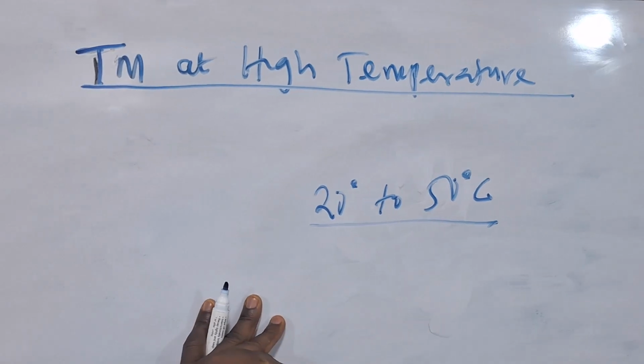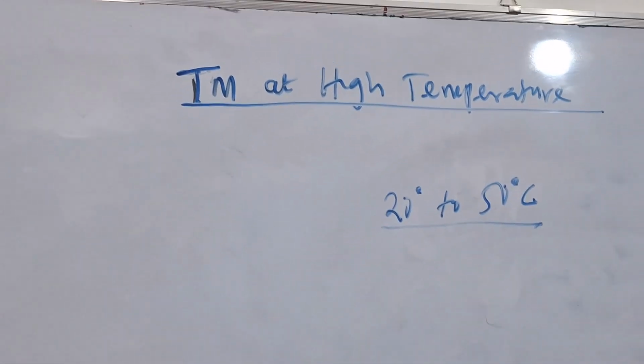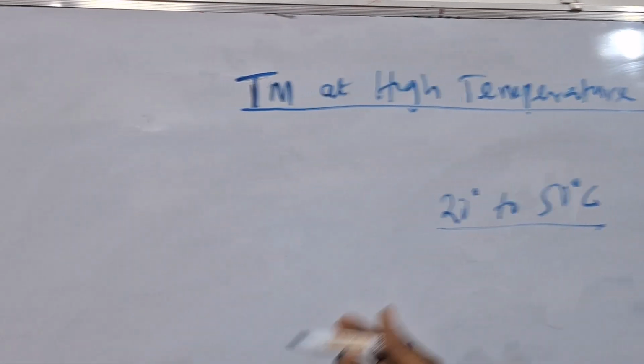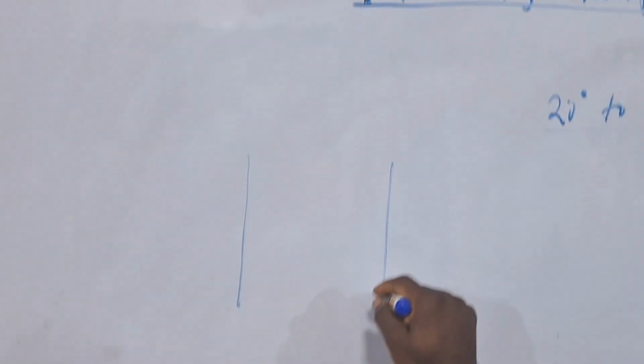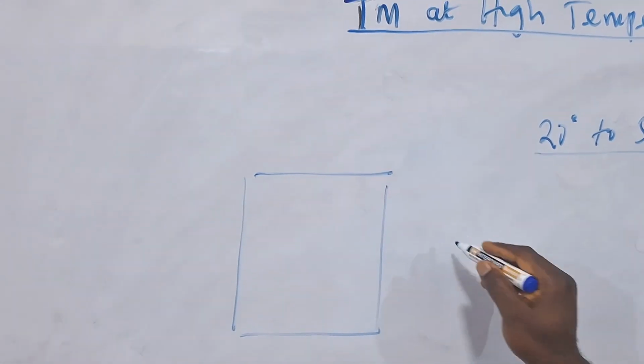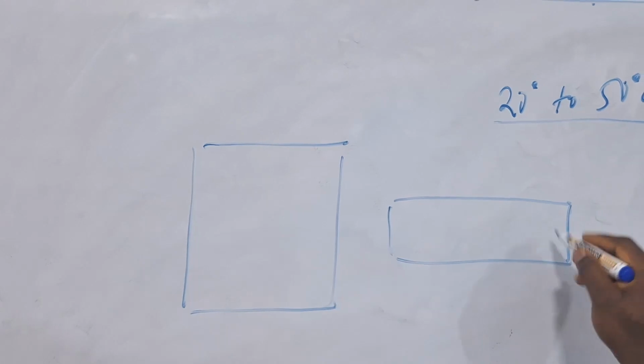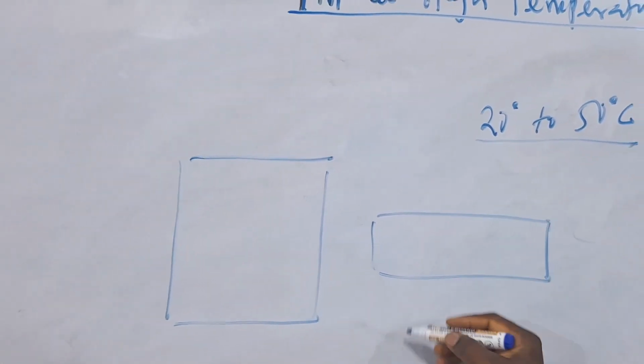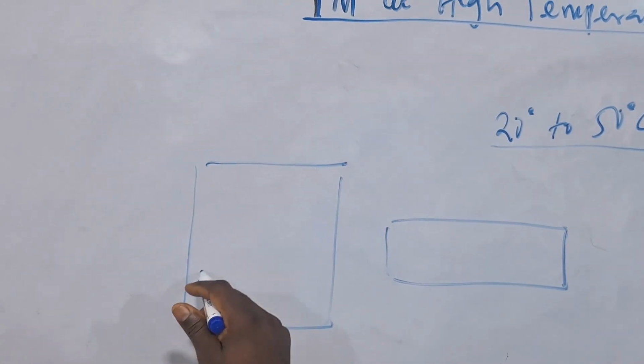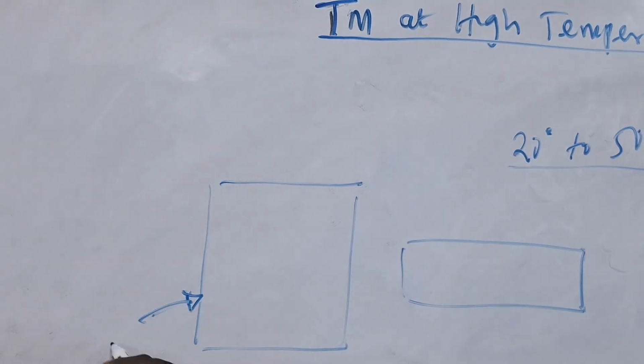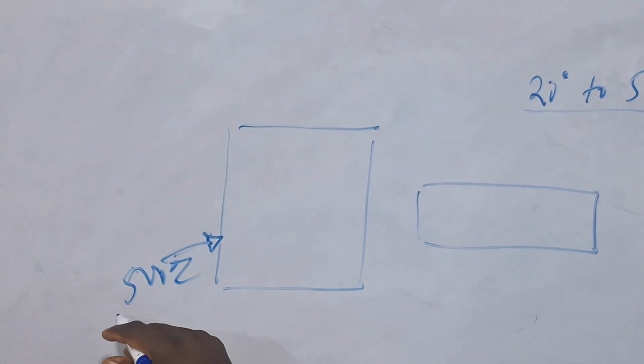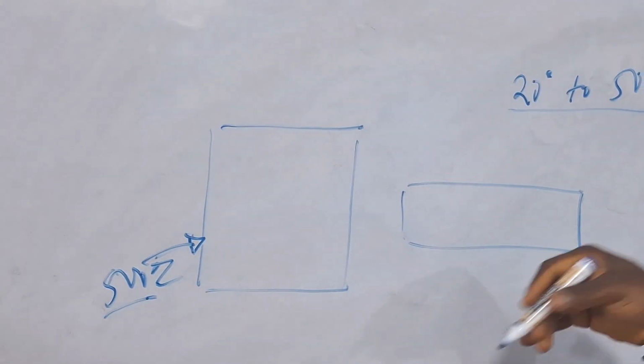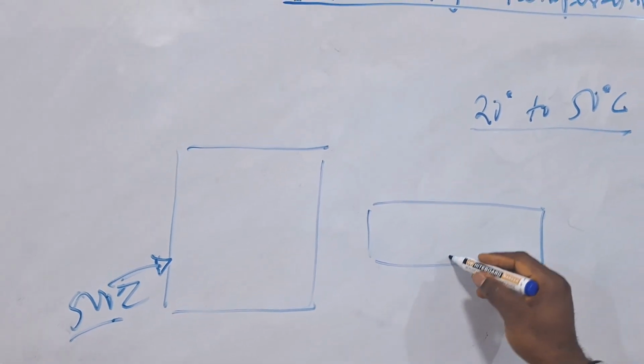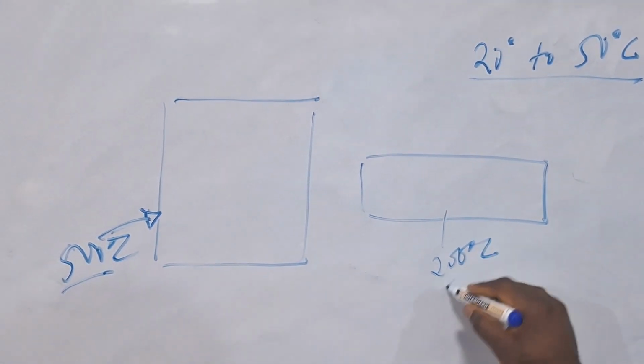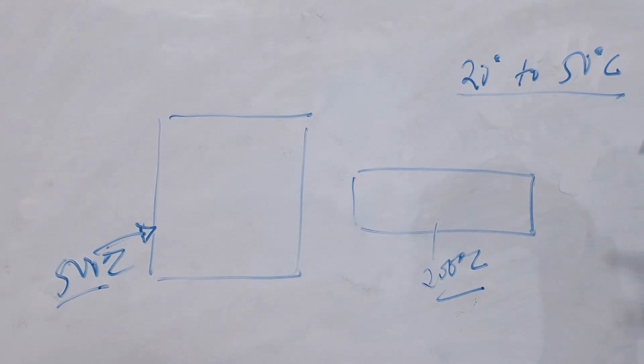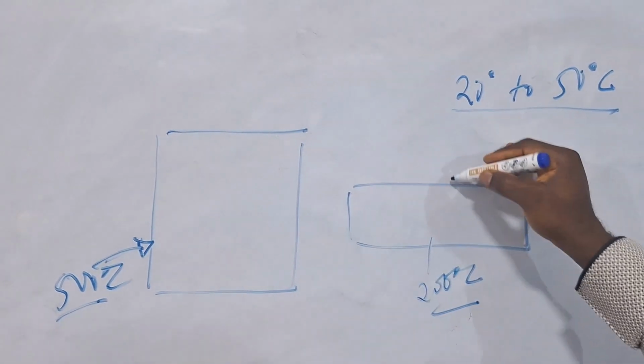Now, when you are taking thickness for a hot surface, let's say you have a boiler, or maybe a heat exchanger, where on the shell side you have very high temperature. You can even have a boiler in some cases when they are not insulated, you can have up to 500 degrees Celsius. In some heat exchangers, you can also have temperatures as high as 200 degrees Celsius. And you want to take thickness on those areas.